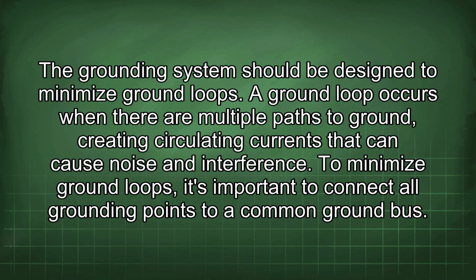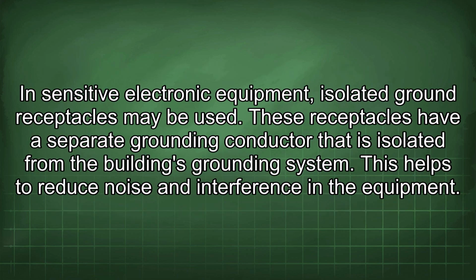To minimize ground loops, it's important to connect all grounding points to a common ground bus. In sensitive electronic equipment, isolated ground receptacles may be used. These receptacles have a separate grounding conductor that is isolated from the building's grounding system. This helps to reduce noise and interference in the equipment.